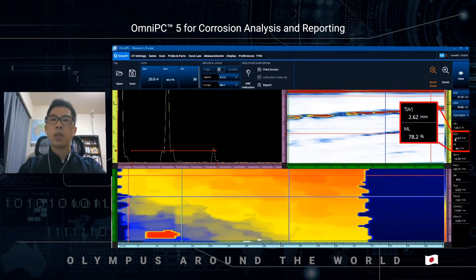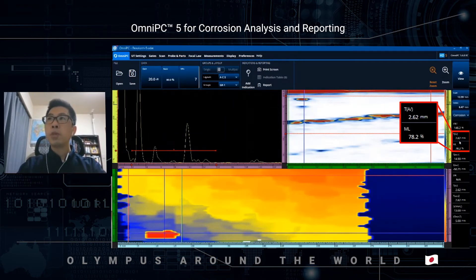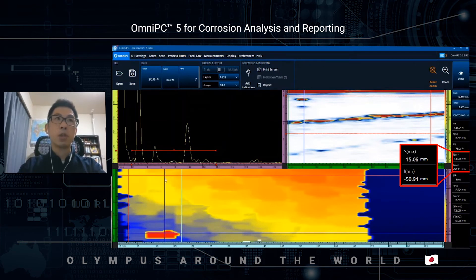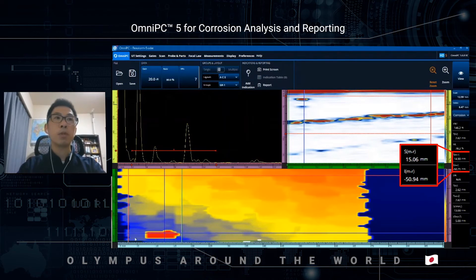TA is the thickness at the specified position and ML is the material loss at the specified position. For example, the thickness and material loss at this position is 2.62 mm and 78.2% respectively. S(M-R) is the distance between the red vertical cursor, called the reference cursor, and the green vertical cursor, which is the measurement cursor. IM-R is the distance between the red horizontal reference cursor and the green horizontal measurement cursor. By using these four cursors, you can create a box or a zone.